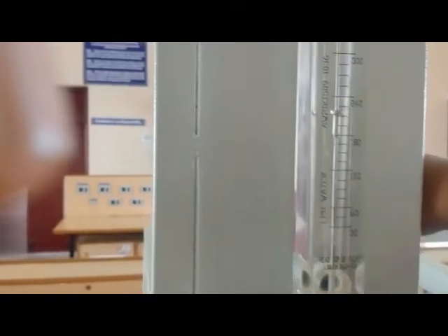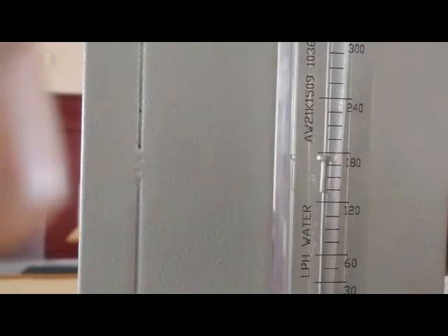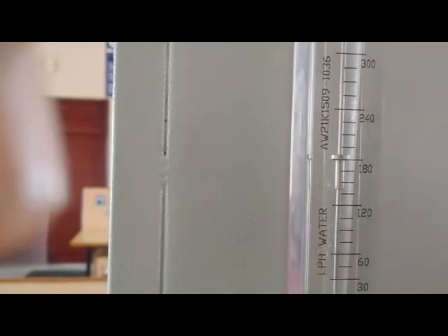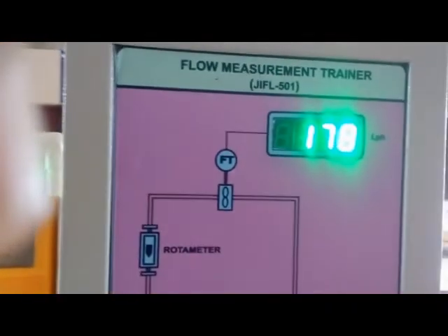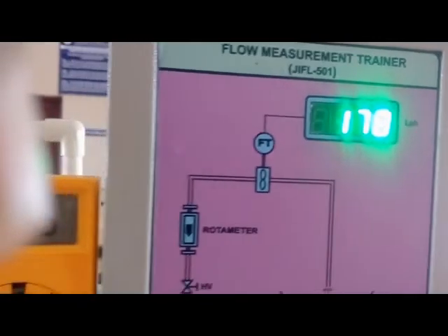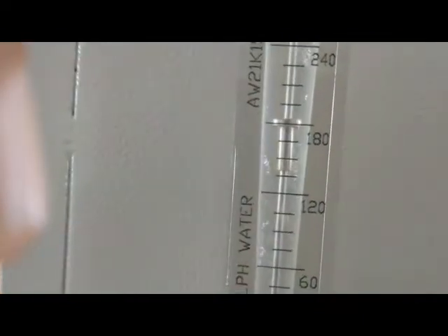Now going to the second reading — bring the rotameter to the next position, which is 180 LPH. You can see the sensor display reads 178, and the voltage across the pin is 3.54 volts.